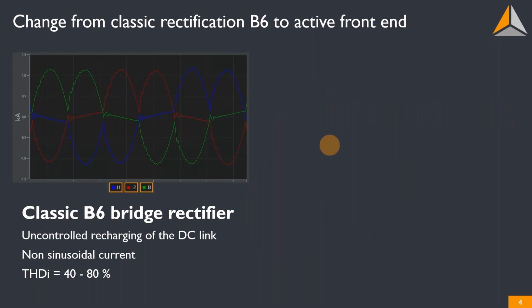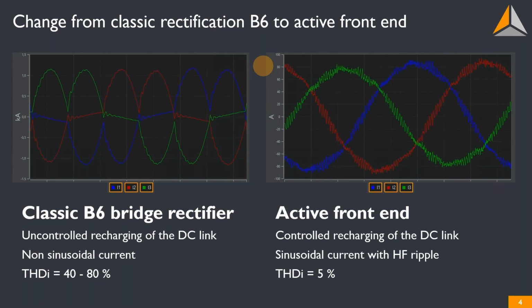So they exchanged their old crane system with a classic B6 bridge rectifier and replaced it with an active front-end inverter. So this is the difference, the current-wise difference. Here we see on the left side the B6 bridge rectifier with uncontrolled recharging of the DC link. So the current doesn't look very appealing to the eye at first glance, not very sinusoidal, and we got a THDI of around 40 to 80% or even higher. With the active front end on the other side, this looks more sinusoidal, and it looks quite good actually at first glance.